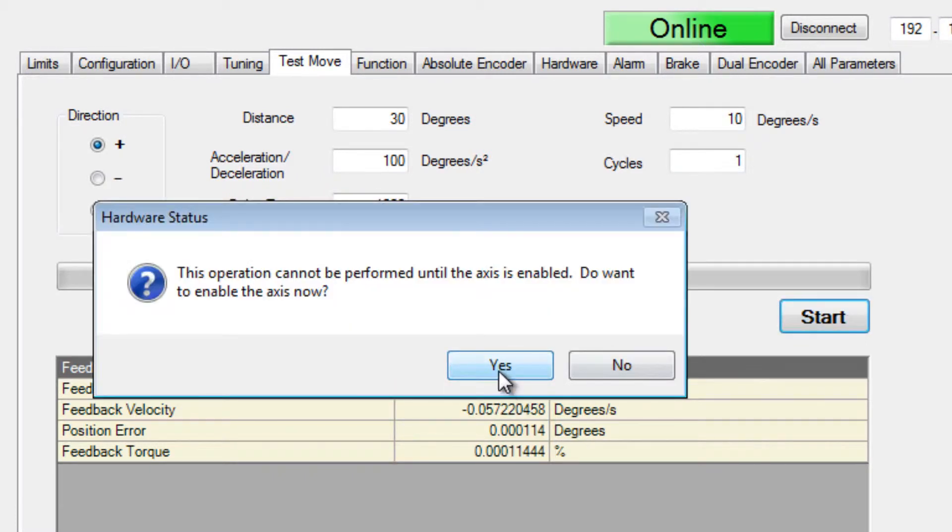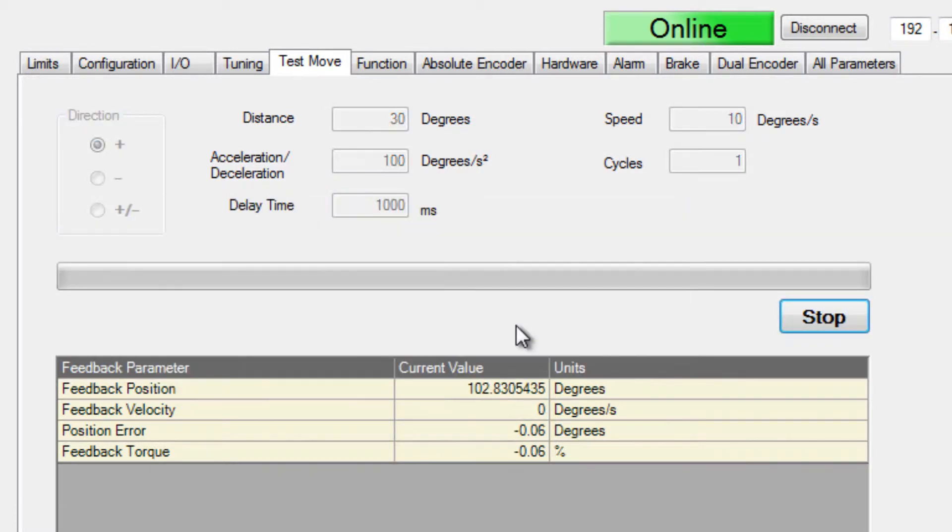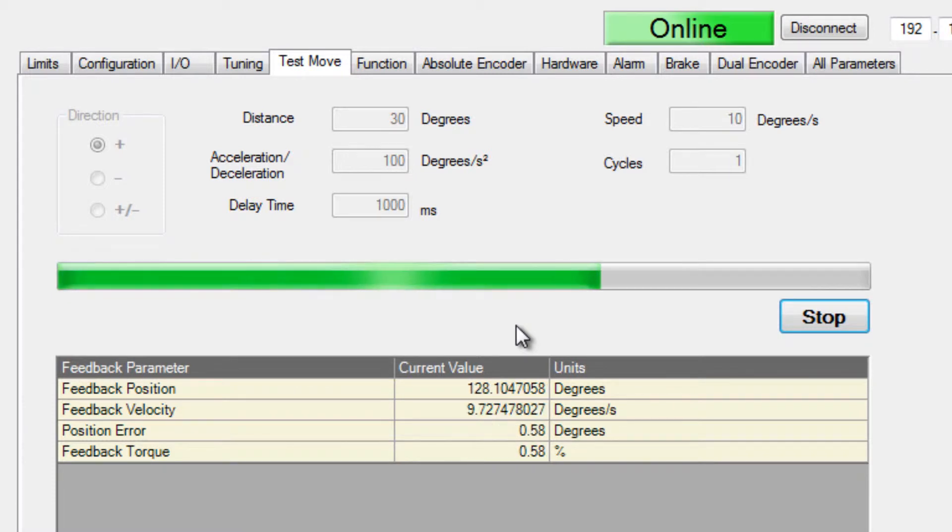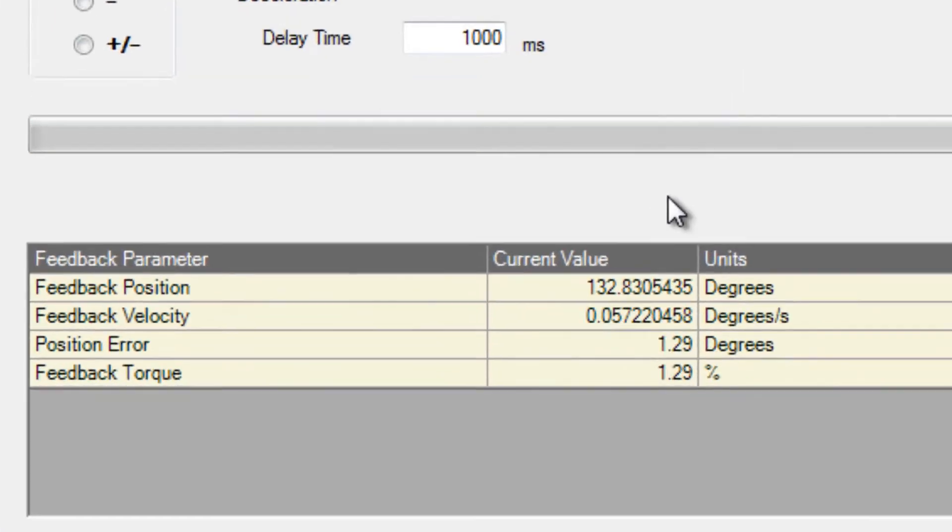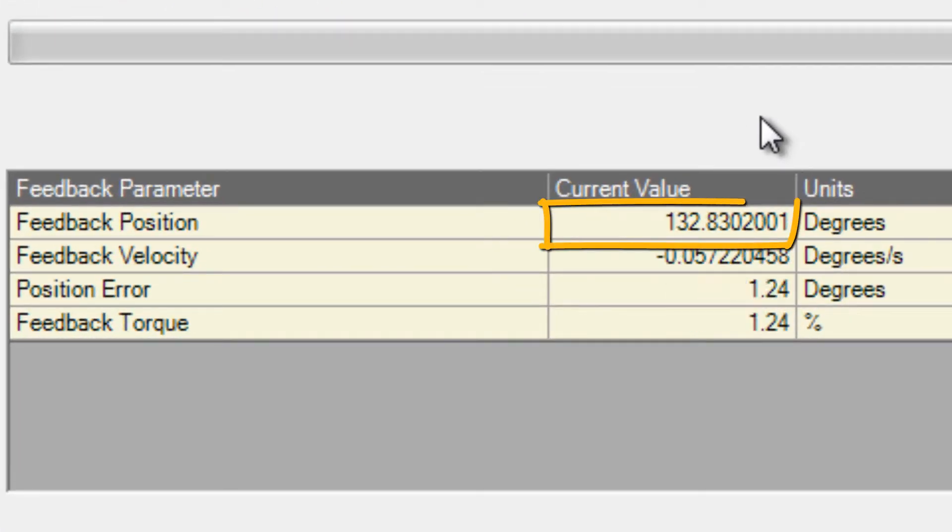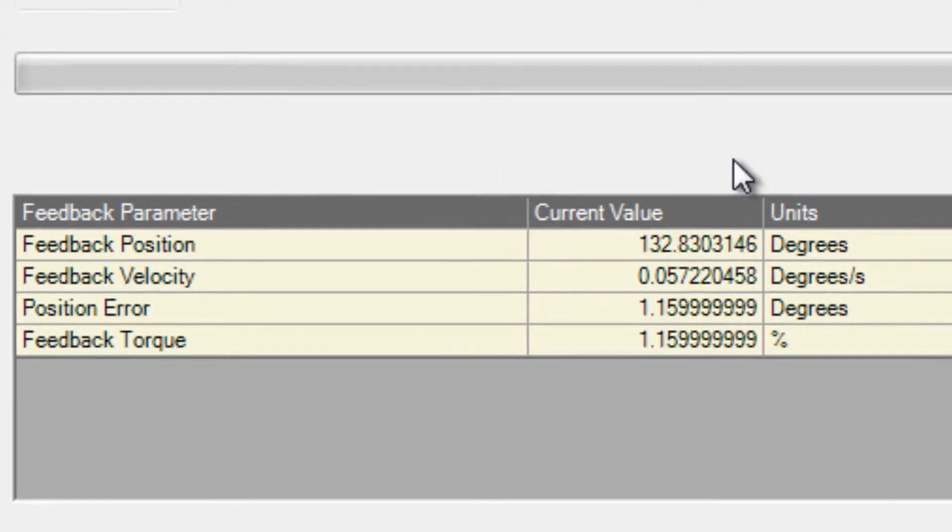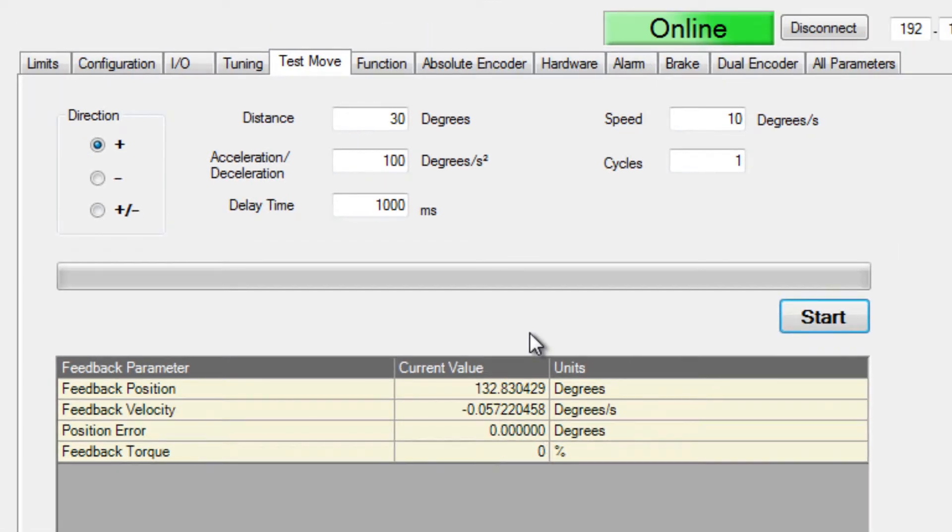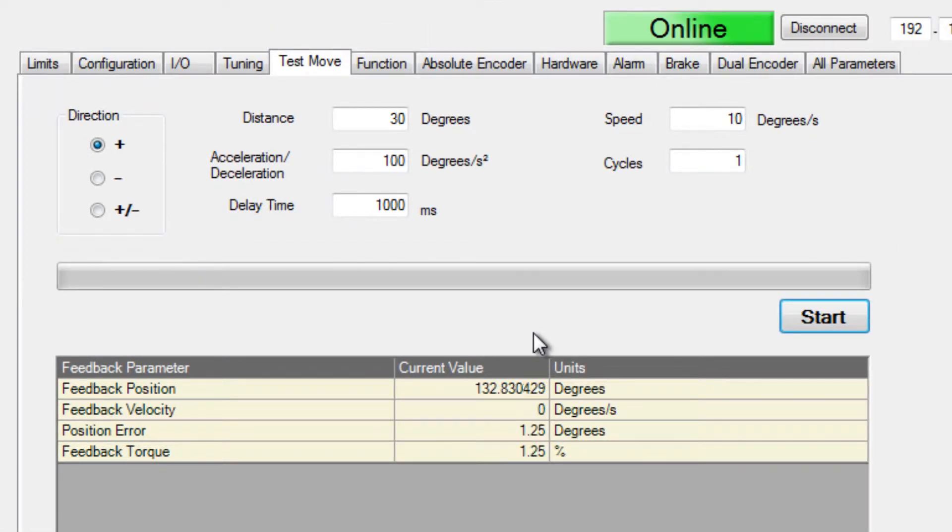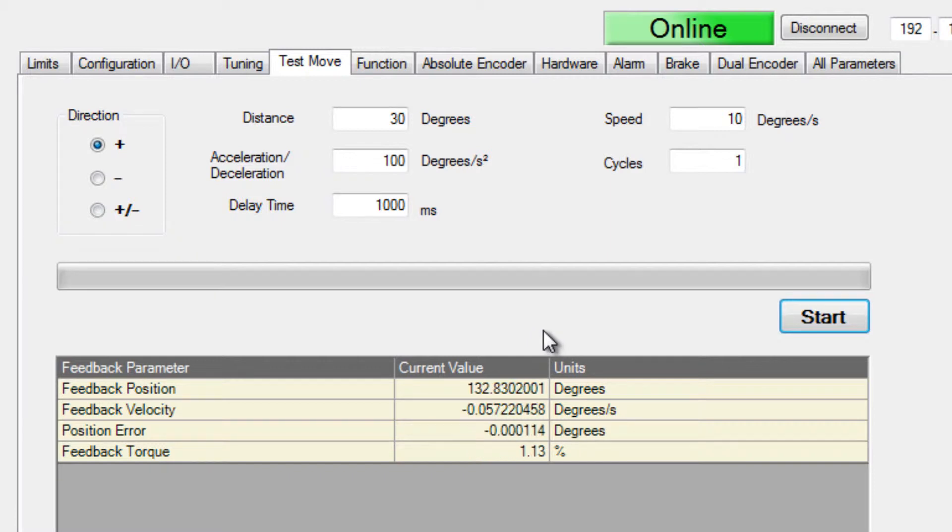Prompted to enable, yes. See the moves taking place and the feedback position has updated to indicate that the move has occurred. With the motor connected to the load, I can confirm that the machine is mechanically moving the distance and direction expected.